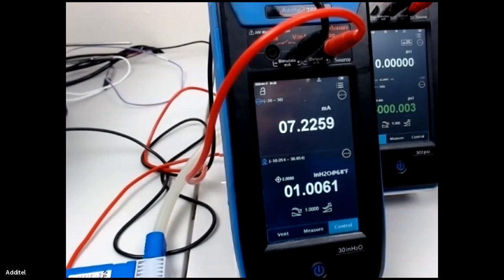We just hit the arrow up, the 1 inch of water up, and it goes up to the next measurement. This happens to be a 5 inches of water transmitter, this Ashcroft transmitter I'm showing you. Literally, I've had customers that have used 1/4 inch of water transmitters.